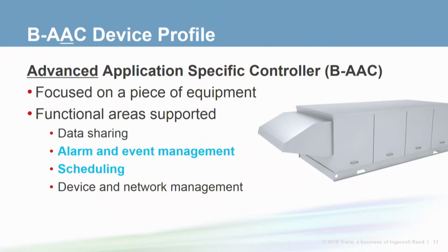The AAC profile, or Advanced Application Specific Device profile, is also targeted at equipment, but includes extra functionality that supports alarming and would allow this equipment to run in a standalone mode. So the functionality specified here is the same as in the ASC profile device, plus support for alarming and scheduling.